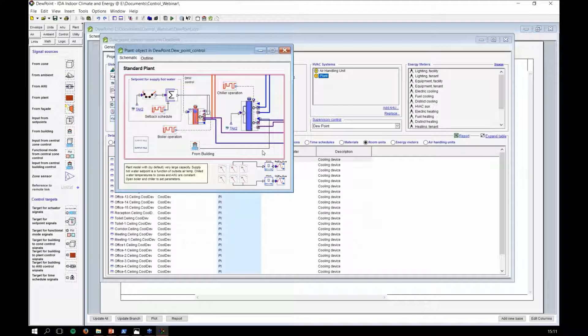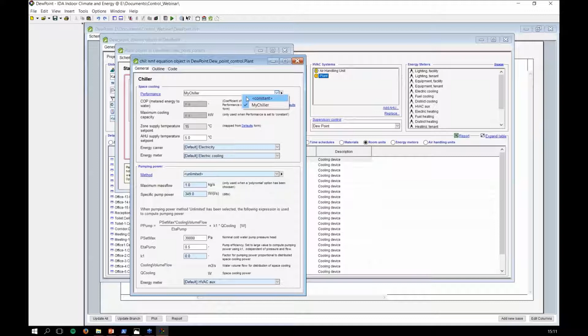One additional thing I did was I went to my COP. By default it comes constant and having unlimited power, but I actually want to study what effect dew point temperature has on the performance of my chiller. So I went in and put a performance curve, and this standard chiller model uses a DOE2 chiller model, which requires that the user import reference coefficients for performance.